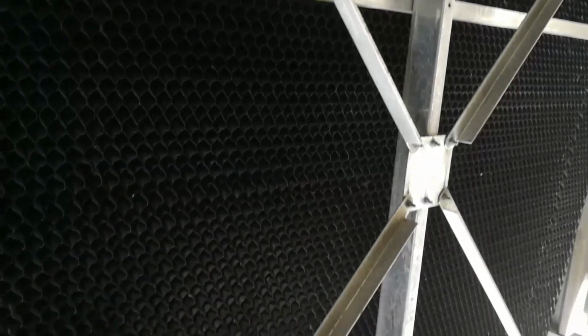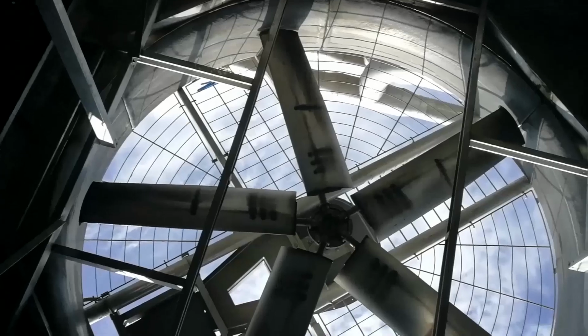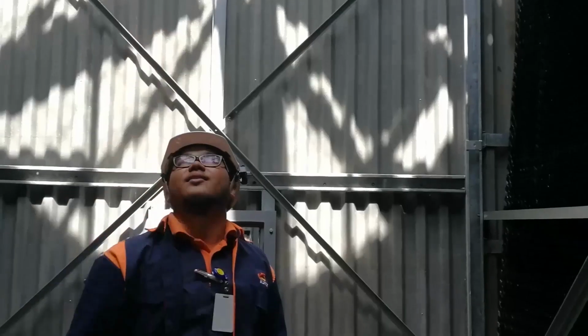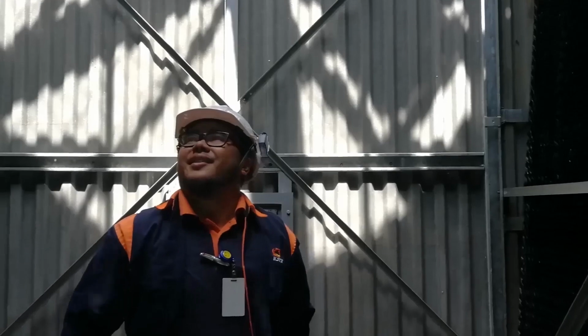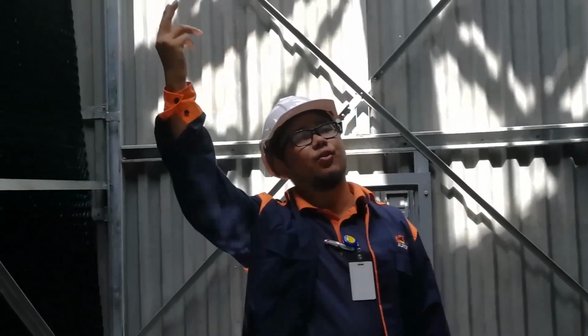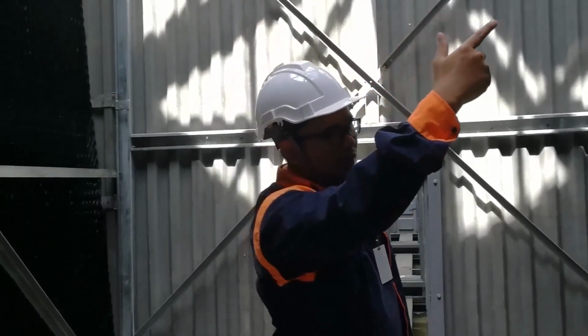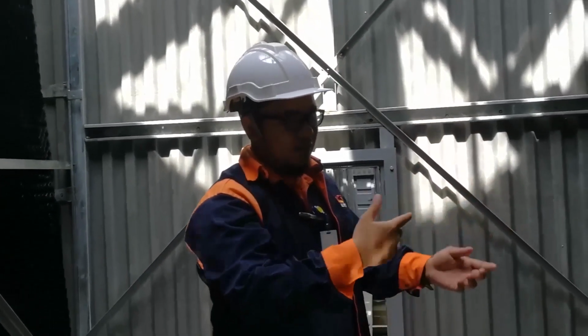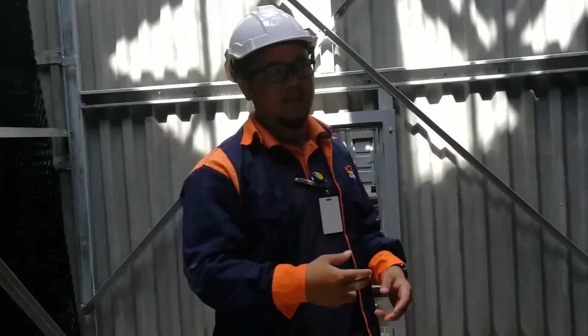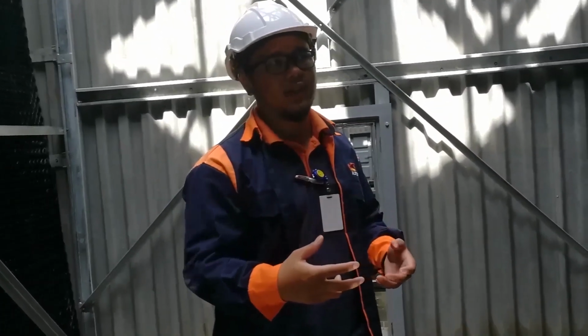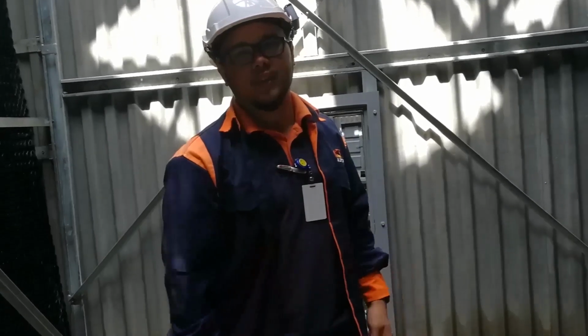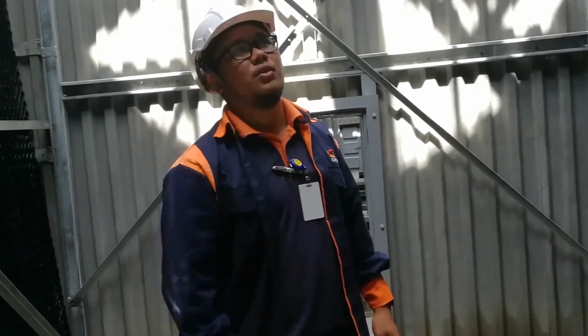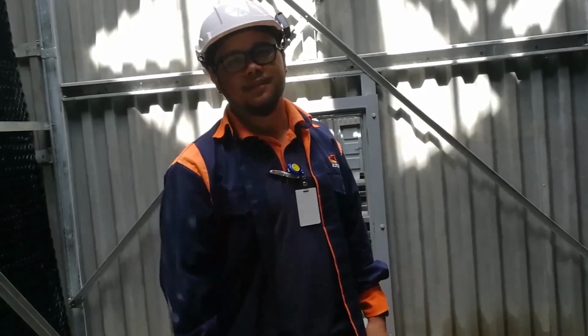As you can see, the black one is what we call infill, and then we have a fan above. The water will come from the top and then go down through the infill slowly, going in contact with the air in order to cool the water, cool the condenser water. So this condenser water is an open system, open loop system.